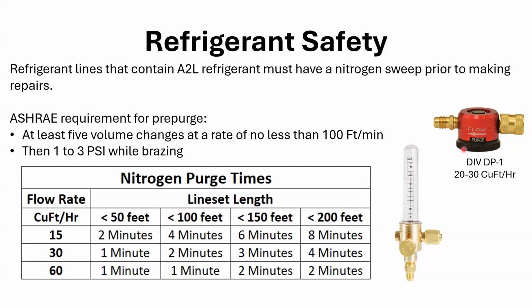You can set them for that braze mode and it just trickles at 1 to 3 PSI through the lines, right? That's all we need, is to establish flow. We just need a little bit of positive pressure to get that flow. We don't need 10, 20 PSI. Plus, try brazing with that pressure anyway. But these devices are nice for that trickle purge.